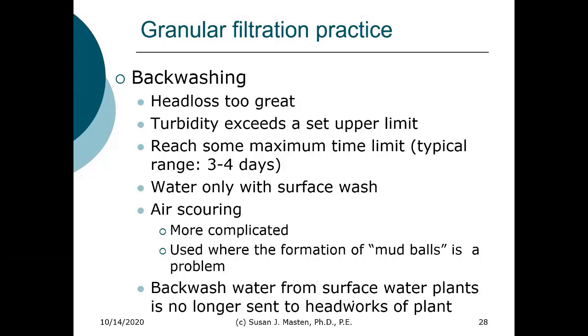This can be done with water only. It can be done with a surface wash. It can be done with air scouring. As I mentioned, air scouring is often used with surface waters where you have the clay, the silt particles forming these essentially what we call mud balls. So just kind of think about when you were a kid, you were playing in the mud, how the clay tends to aggregate together. It used to be that the backwash water from a surface water plant could be sent back to the headworks of the plant, but that's no longer the case.